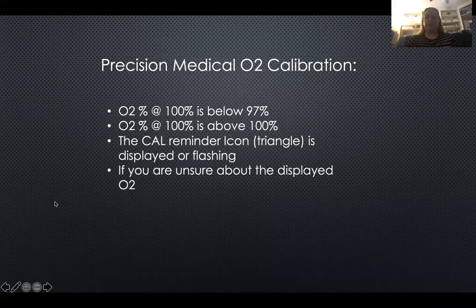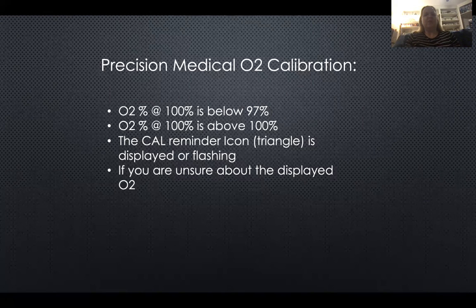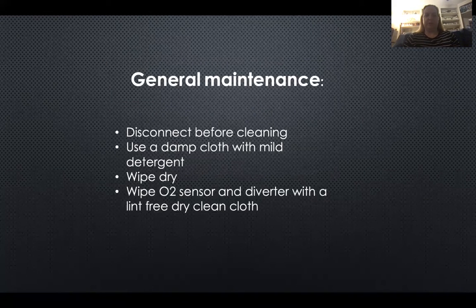So how often should you calibrate your O2 analyzer? According to Precision Medical's catalog, they recommend that when your O2 is set at 100% and your sensor is reading below 97 or above 100, it should be calibrated. Or if the cal reminder icon, it's usually a triangle, is displayed or flashing, that usually means the machine needs to be calibrated. Or if you're just unsure about the O2 displayed.